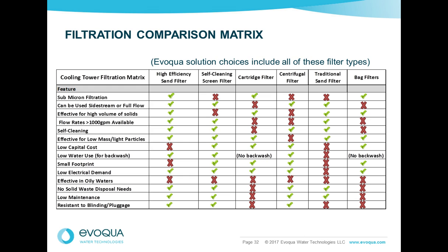They've been around. But remember, that low capital cost is offset by high maintenance needs, and the fact that you have to deal with and dispose of those cartridges or bags. Some people reuse the bags, but it's a pretty dirty proposition to be cleaning out the bags and reusing them, and eventually they're going to have to throw them out anyway. Over the years, I've seen cartridge and bag filters installed on a lot of systems. The issue became that companies got leaner, and maintenance guys didn't have time to deal with changing these cartridges.